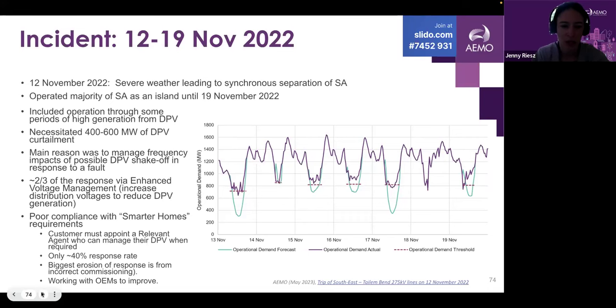Most of this response was delivered by the DNSP, our distribution network provider, through what they call enhanced voltage management, which they use to increase their distribution voltages to about 1.03, 1.04 per unit, deliberately tripping off PV generation in these periods. That was implemented as a last resort mechanism. It's obviously not ideal to increase distribution voltages higher than nominal, but it was put in place to deal with a lot of these legacy PV systems that didn't have any active controls.